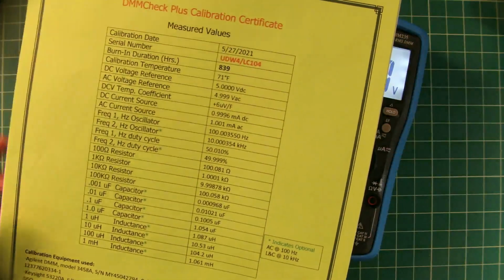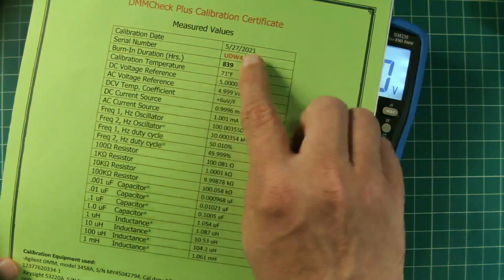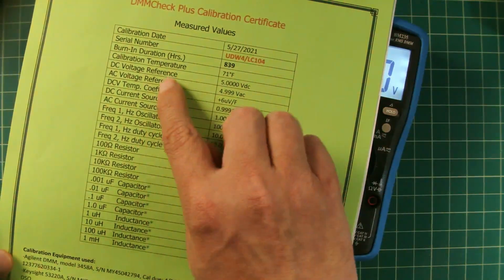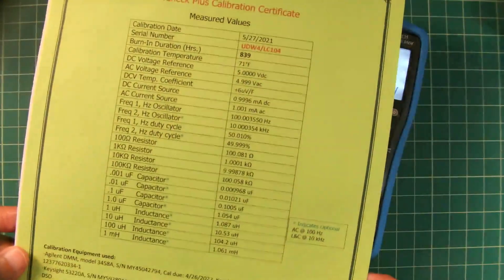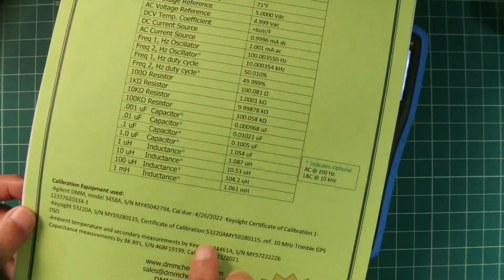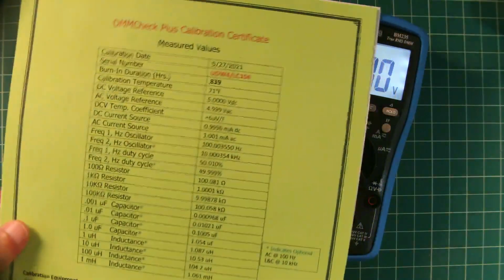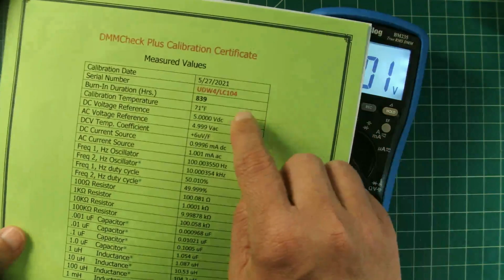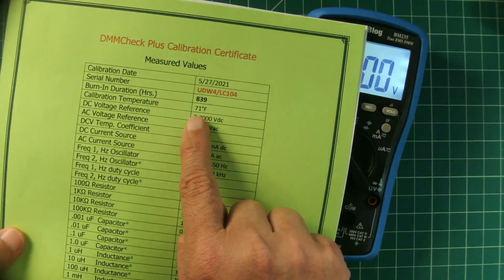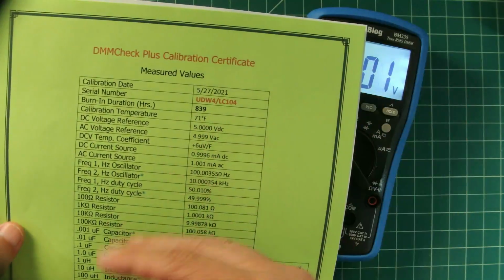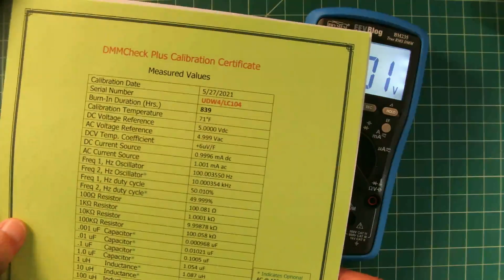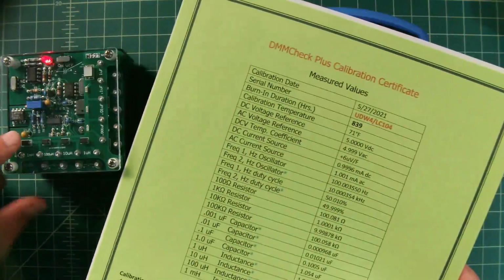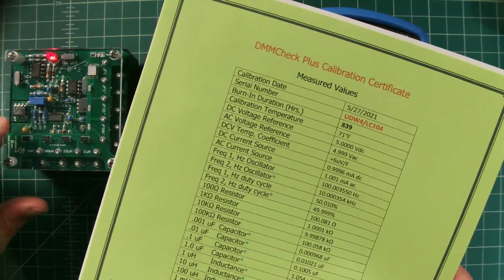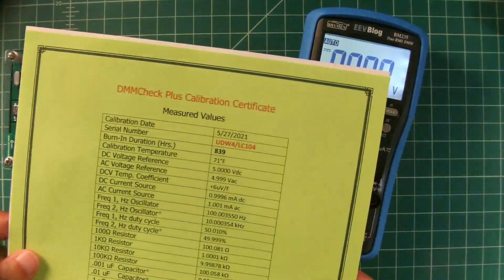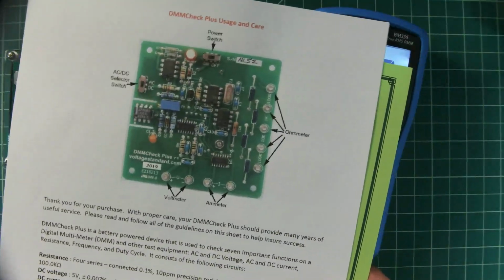So your DMMCheck Plus will come with the measured values or the calibrated values for the different options that you selected and what you built. Down here, it will tell you when it was calibrated, and it will tell you the equipment that was used. Also, when you turn this thing on, you want to leave it on for a little while to warm up. So it was calibrated at 71 degrees Fahrenheit. Now, most of us know that depending upon the temperature, your ambient temperature, or the temperature of the device under test, in this case, the DMMCheck Plus, you could get different values. And so it's a good idea to turn this on and leave it on for a few minutes, which is what we're doing.